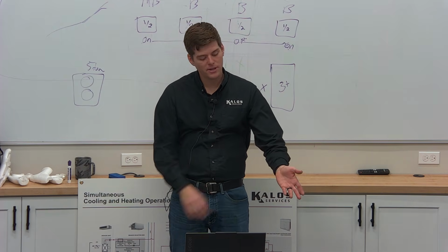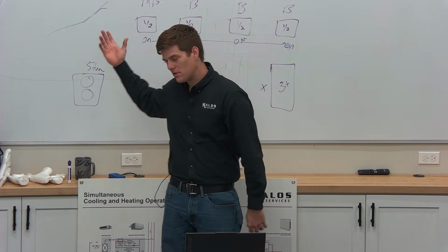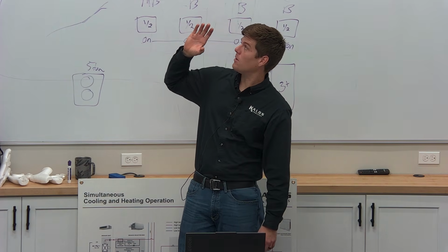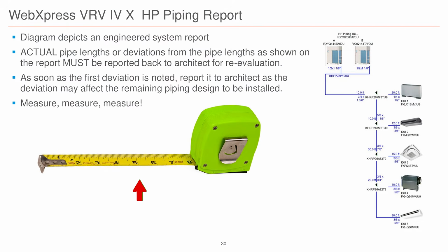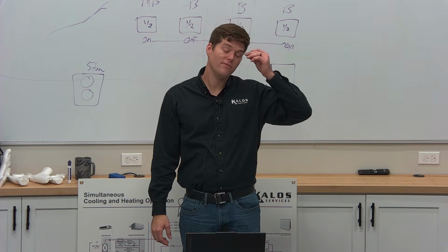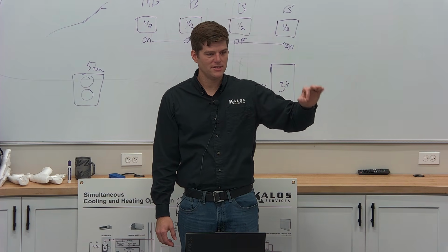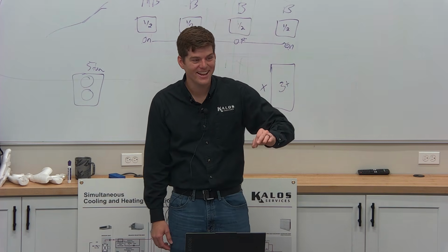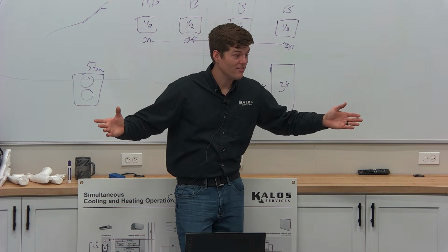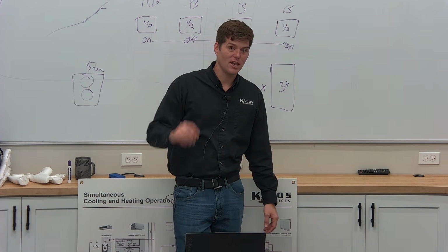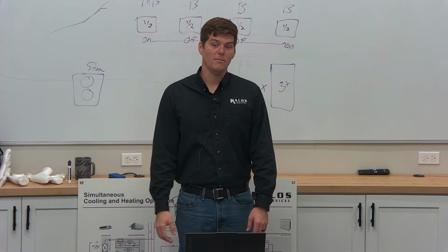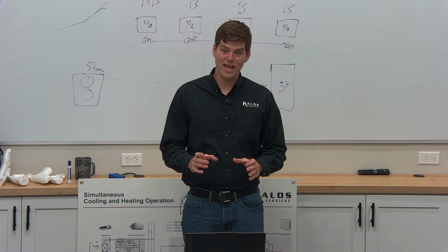So we talked about the Refnet installation. We talked about traps in the system. But it all comes down to this beautiful tape measure here, right? Using it, ensuring that it's accurate. And I don't want to come back and find that you've got 15 feet, 0.8777 inches on this line. Sure, go for it. I don't care, right? But I can tell you that I've looked at a lot of these reports over the years, and when it's a round even number, I call BS.